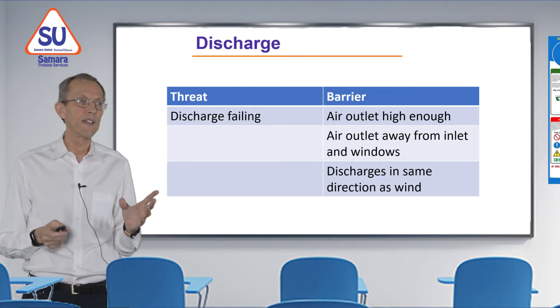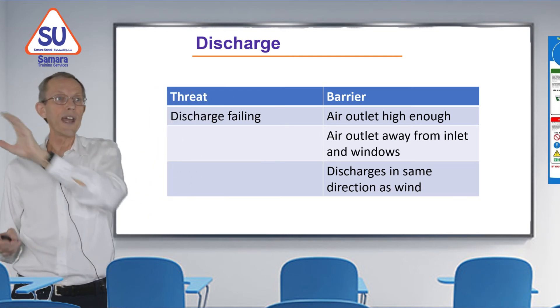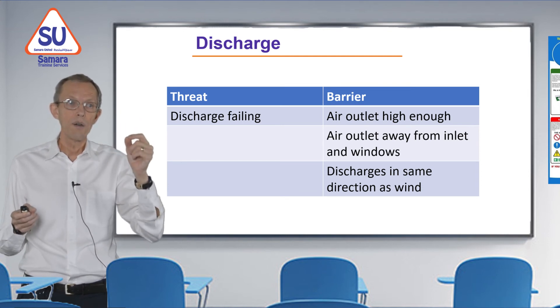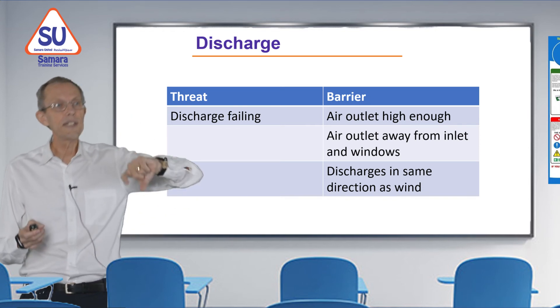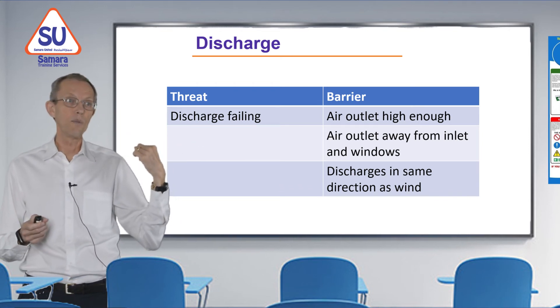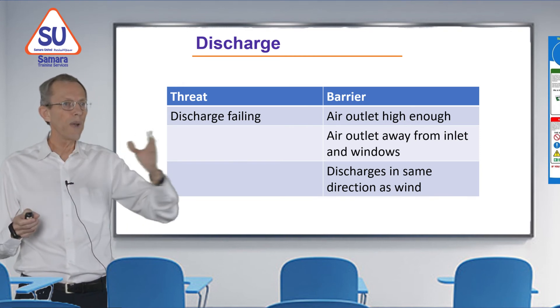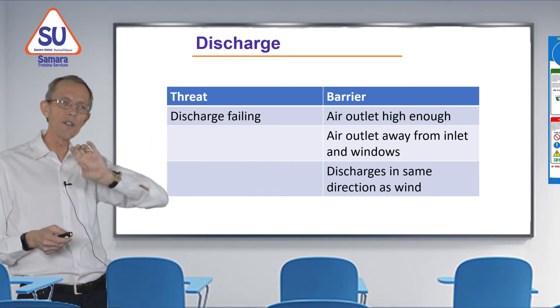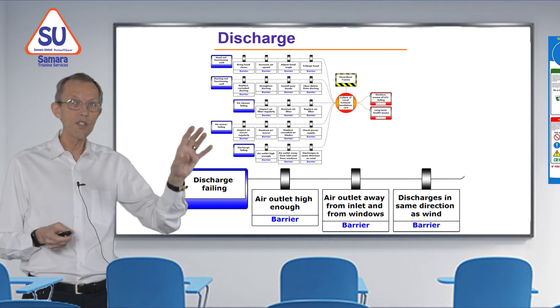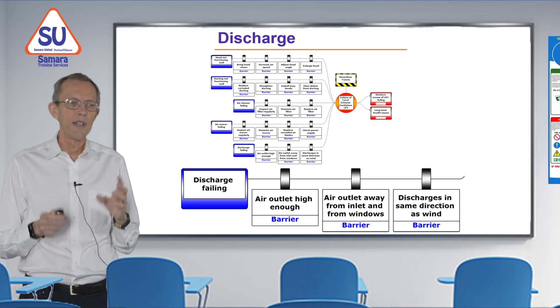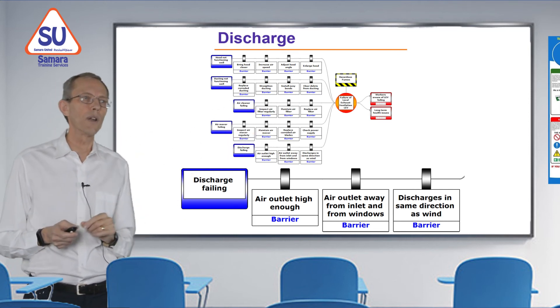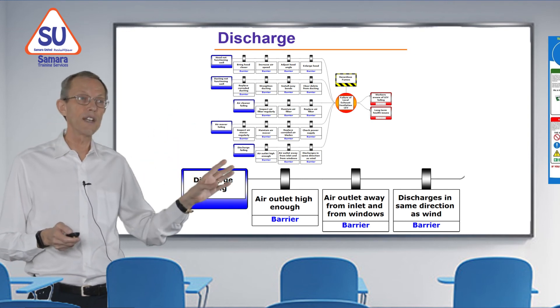The last threat is the discharge failing — where the cleaned air gets blown out. If we don't have it high enough, that air, which still contains some contaminant, will be in an area where people might breathe it. So we need it high enough. We also need to make sure it's away from windows — we don't want to blow exhaust air into a nearby office. And if there's a prevailing wind direction, we want the vent working with the wind to help disperse remaining fumes. On the diagram: discharge fails — move the outlet higher, move it away from windows, and angle it to work with the wind. One side of the bow tie is now complete.